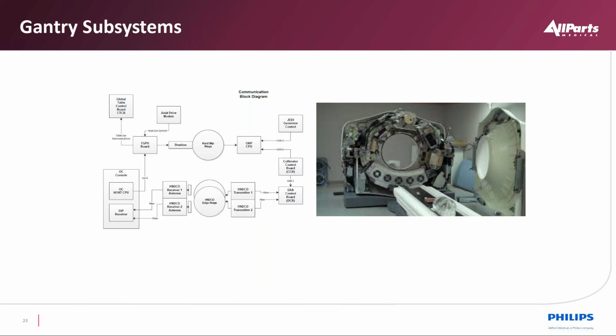This represents more of that detail in a more simplified view, so that we can show the names of the components particular to the VCT, like the generator control. We'll deal with the high voltage inverter, the tube, the tank, and producing X-ray. Then we have the collimator control and the DAS control. Those are all on a rotating ring, and we have what we call slip rings that transmit the data, either through brushes or, on the newer systems, RF with fiber optics feeding and receiving from the RF transmitter rings. Then we'll have hard rings for power as well. As you can see, the walkthrough is somewhat the same, but then we have the DAS interface processor in the lower left.